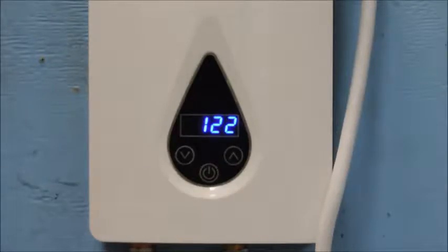An E1 error code happens when the heater reaches an outlet temperature above 60 degrees Celsius or 140 degrees Fahrenheit. This usually happens because of a quick drop in water flow and will usually resolve itself once the heater reaches a lower operating temperature. To correct this, either reduce the requested temperature or increase the water flow.